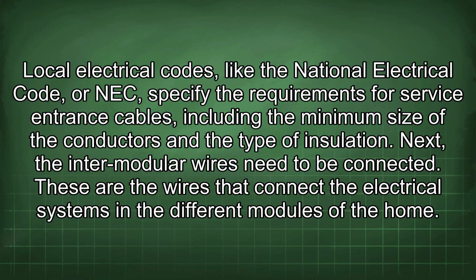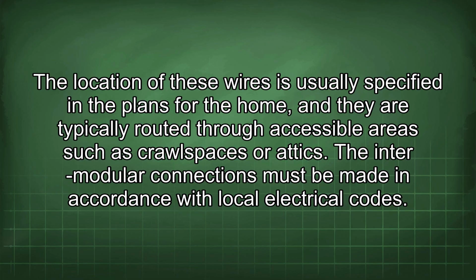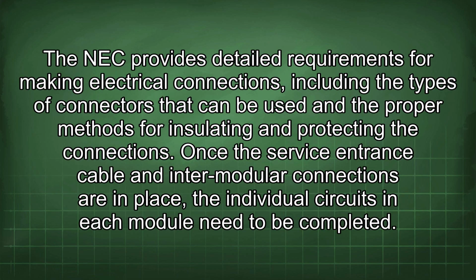Next, the intermodular wires need to be connected. These are the wires that connect the electrical systems in the different modules of the home. The location of these wires is usually specified in the plans, and they are typically routed through accessible areas such as crawl spaces or attics. The intermodular connections must be made in accordance with local electrical codes. The NEC provides detailed requirements for making electrical connections, including the types of connectors that can be used and the proper methods for insulating and protecting the connections.